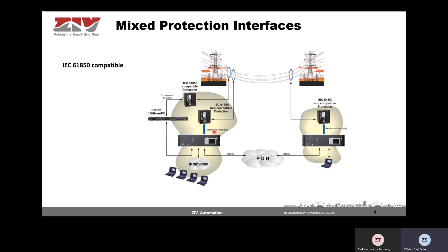This is very useful in the case of migration of protection relays to the IEC 61850 standard, as it helps to have a smooth migration. In that case, we have a teleprotection link where, in one substation, we have a non-61850-compatible protection, and at the other side we have a mixed protection interface. This is the first application.